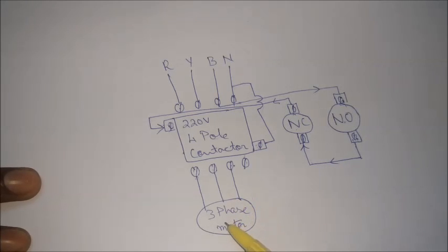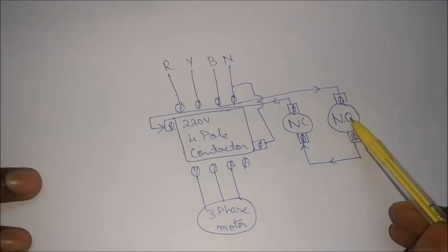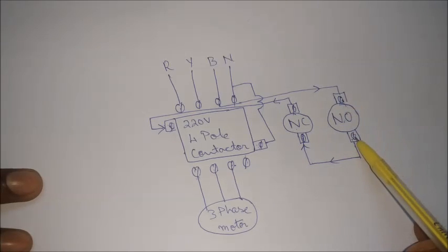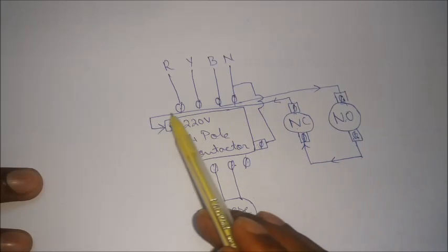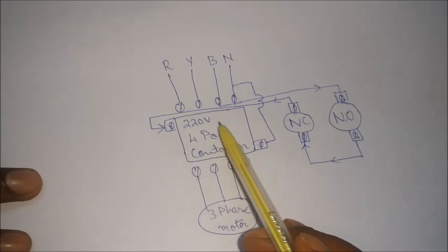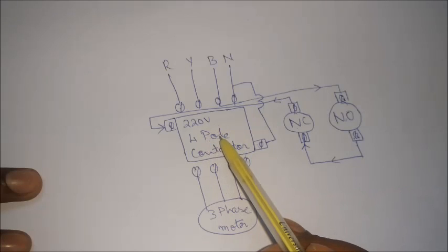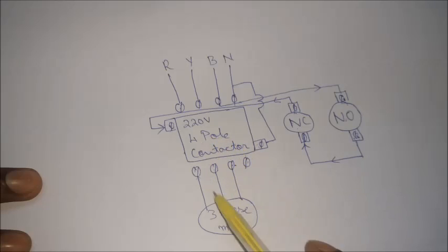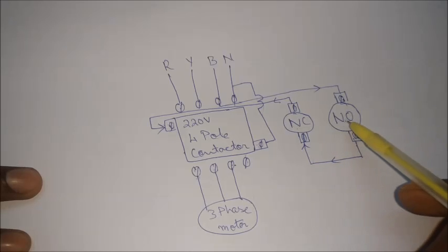But we have a problem here. Once the NO switch is released, current from here does not flow out of this point. Hence there is no current here to activate this solenoid coil inside the 4-pole contactor. Hence the link breaks and the motor goes off. So you cannot keep your finger always pressed on this.